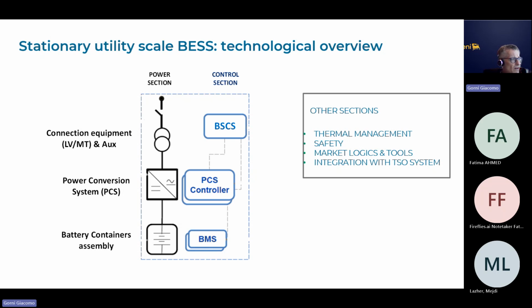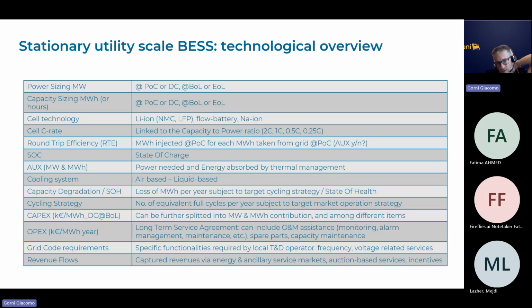Each container can reach something like 40 feet and can be up to 5 megawatt hours, if I remember correctly. So it's a decent footprint coming together with the storage needs - if I need 50 megawatt hours, it will just be 10 containers, not that much. Then there's a typical list of specifications - a bit boring, but important - to keep in mind when sizing and designing an energy storage system. It's not only power and capacity; many other aspects need to be considered.